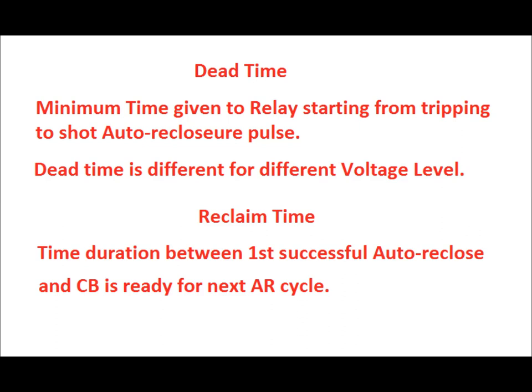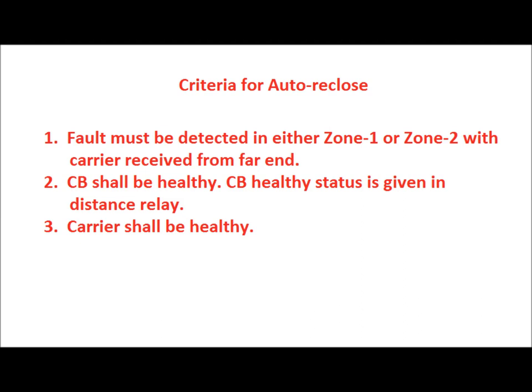Reclaim time is the time duration between the first successful auto reclose and when the circuit breaker is ready for the next auto reclose cycle. For example, after the dead time the relay sends an auto reclose pulse and the circuit breaker normalizes. If a fault is then sensed, the relay sends a trip signal, the breaker opens, and after another dead time the relay sends another auto reclose pulse. Reclaim time is essentially the time between two successive auto reclose operations.